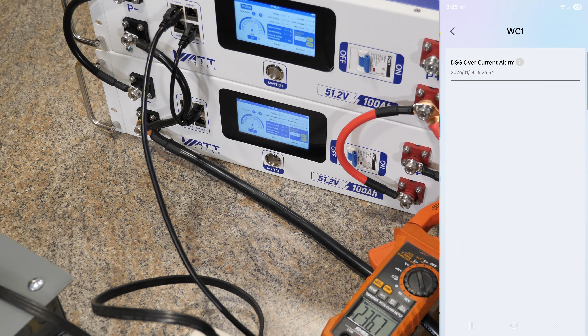So what I'm gonna do now is turn on the space heater on low. That's 218 amps. I'm gonna go to high. It's 236. If we look at battery 1, we're doing 115 amps, and we're getting a warning right now, the discharge overcurrent alarm.